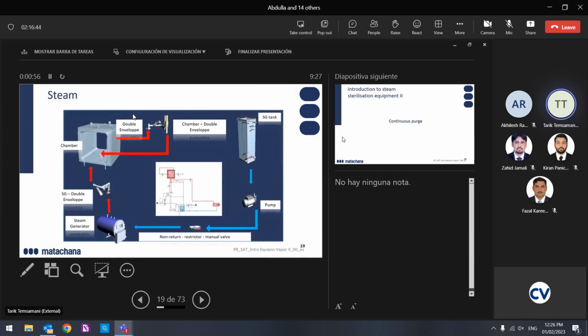Even the SG tank inside the heater, no? The tank, what is the reason? Just explain to them. The heater, the tube, the tank inside, this one? Yeah, to maintain the RO temperature. The steam generator tank didn't have any temperature probe, only a float switch or level switch.